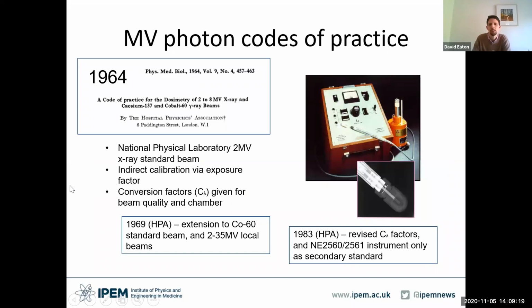The other interesting aspect to look back upon, and I guess this is before the times of many, if not all of us on this call: when was the first UK code of practice? Well, looking back through the archives of PMB, we find that in 1964, there was a code of practice for the dosimetry of 2 to 8 MV X-ray and caesium-137 and cobalt-60 gamma ray beams. This code of practice was based on a standard 2 MV X-ray beam produced and sited at the National Physical Laboratory. And apparently by this stage, the majority of clinical centres were using the NPL as a service to calibrate their local equipment.